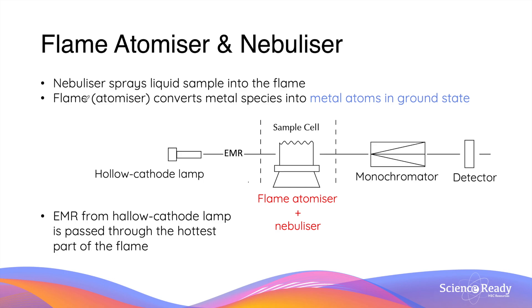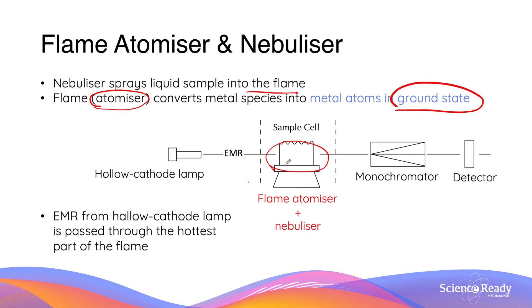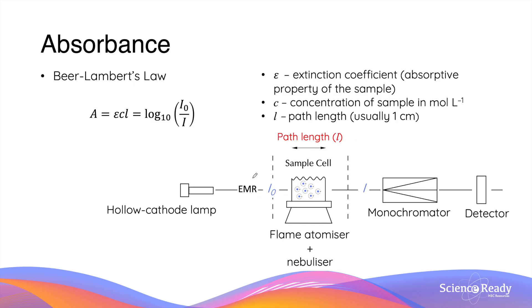A nebuliser sprays the liquid sample, which contains the metal we want to measure, into the flame. In AAS, the flame is responsible for converting metal species in the sample into metal atoms in the ground state — that is, metal atoms whose electrons are in their normal orbits, not yet excited. This is why the flame is referred to as the atomiser. The EMR produced from the hollow cathode lamp is passed through the hottest part of the flame, where metal atoms in the ground state are present. Since the EMR produced by the hollow cathode lamp is characteristic of the metal being analysed, the metal atoms in the flame will absorb this EMR to reach an excited state. Due to this absorption, the amount of EMR before the flame is always going to be higher than what comes out of the flame.